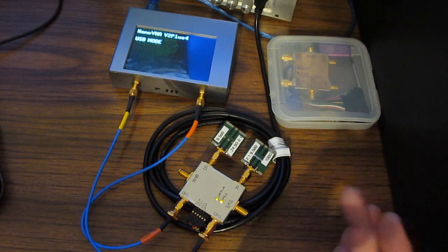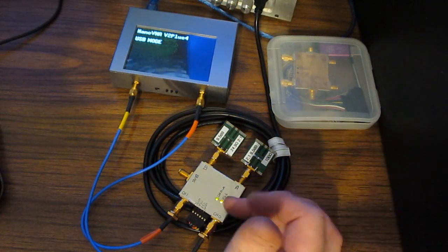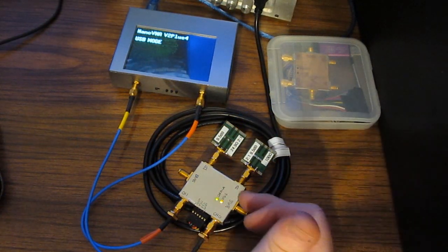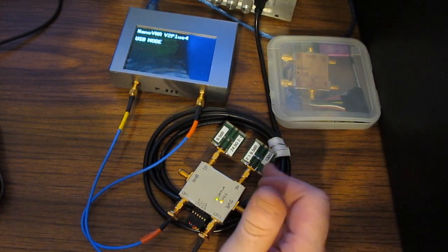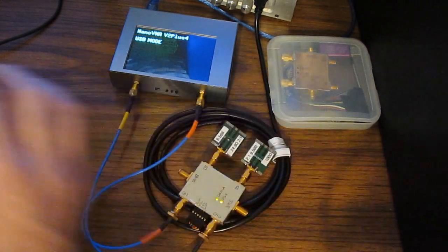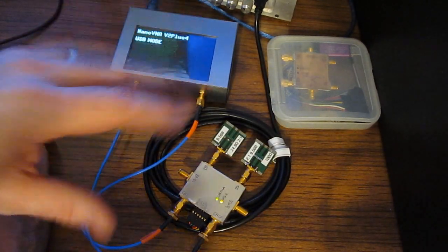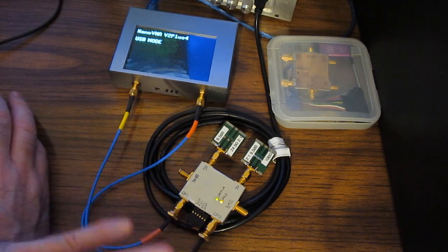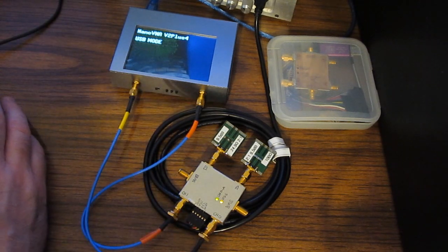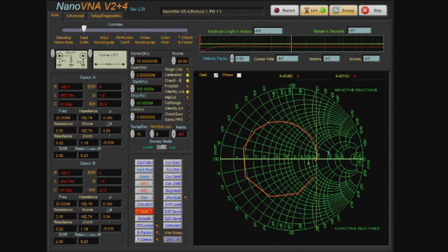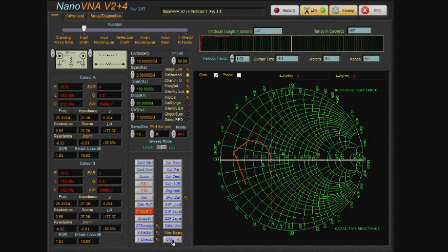For this next test, I have our solid state transfer relay attached to port A with a 100 ohm resistor, and port B with a 25 ohm resistor. It doesn't really matter. I have not calibrated the unit. Let's change the state of the transfer relay and you can see how that changes the shape of the waveform.